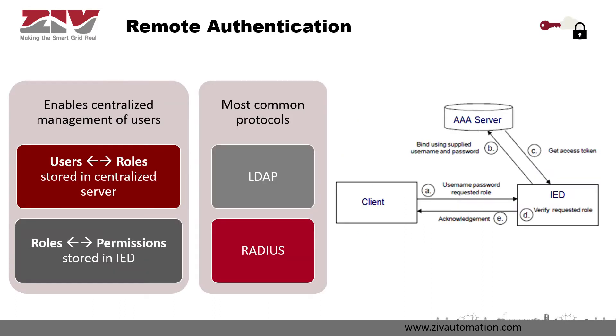It's very common and advisable to manage users in a centralized server, so the IED uses remote authentication to authenticate users, as we can see in the picture on the right. The client provides a user and password to the IED, and the IED authenticates the user against the centralized server. If authenticated properly, the IED gets the role of that user from the server and verifies it, then determines the corresponding permissions and lets the user perform the operation.